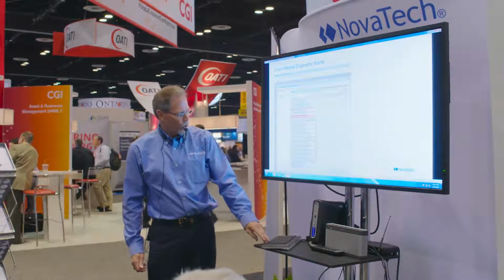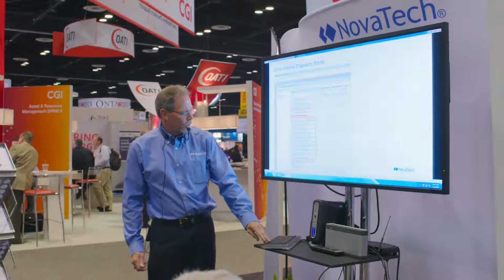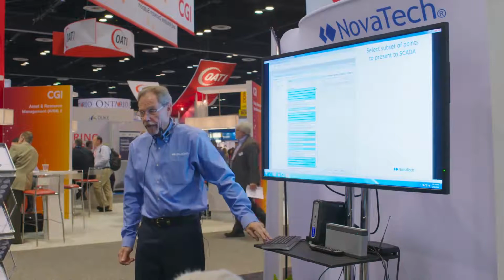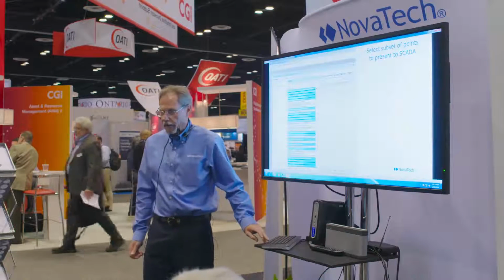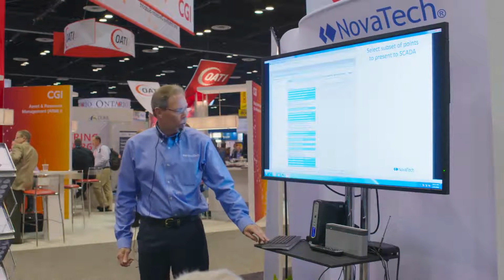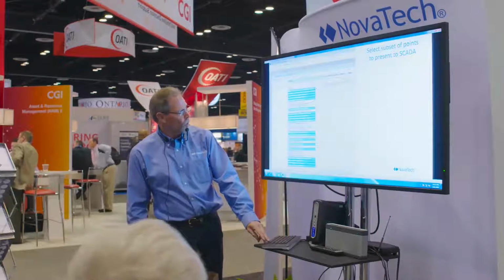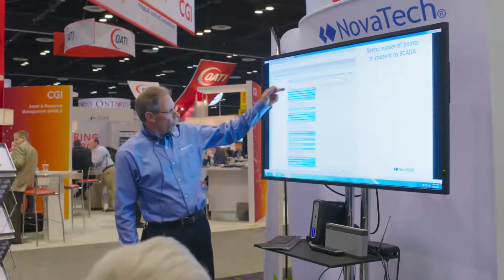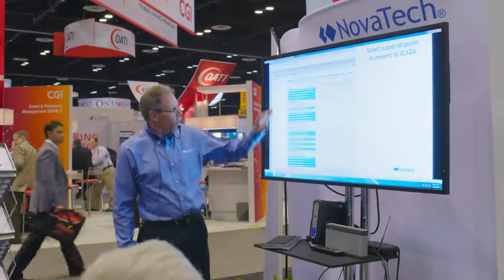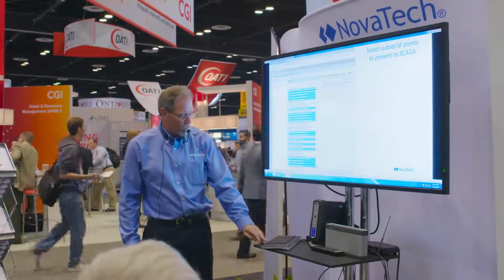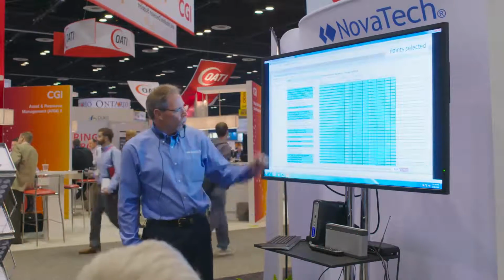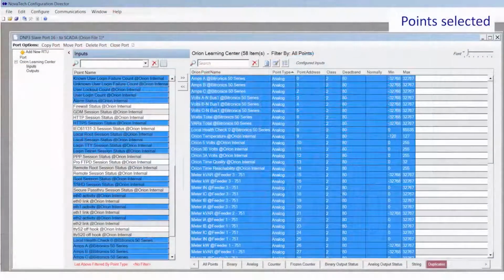Okay, so these are some new security points that we've added recently. Not required by NERC-CIP, but it sure makes for handy application if you are concerned about if it's a particular NERC-CIP substation. So typical security points that you might want to map over to SCADA as well. So I grab the values, map them over, and now these are the values that are going to be presented to SCADA. So those are the points that SCADA is going to request and receive from the Orion on that SCADA port.